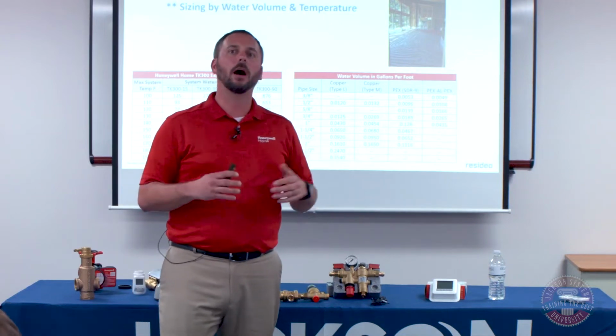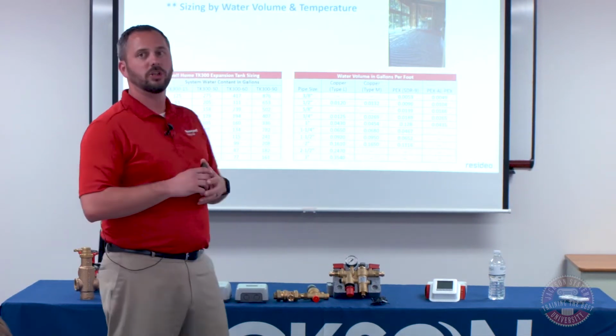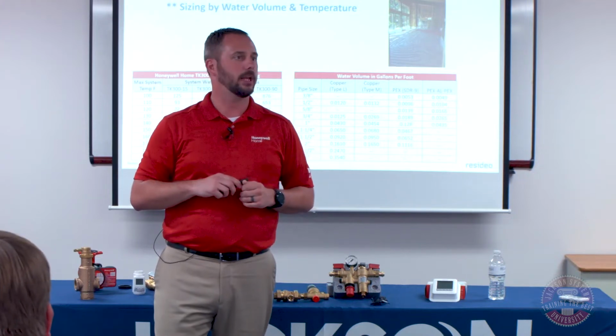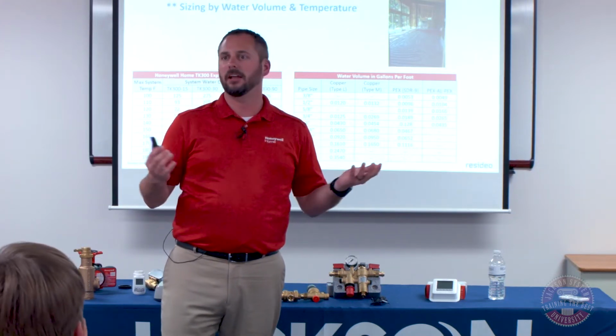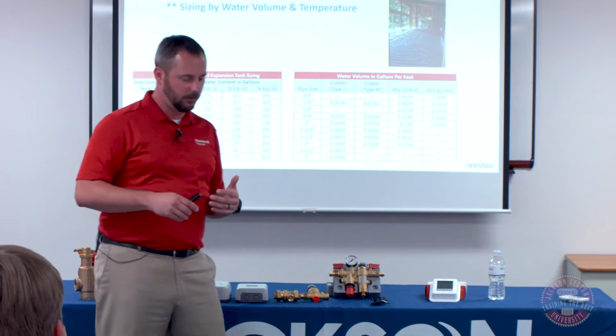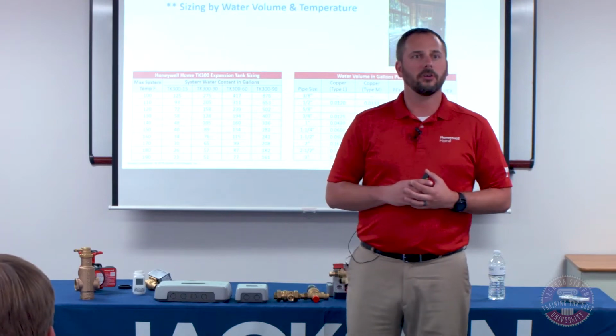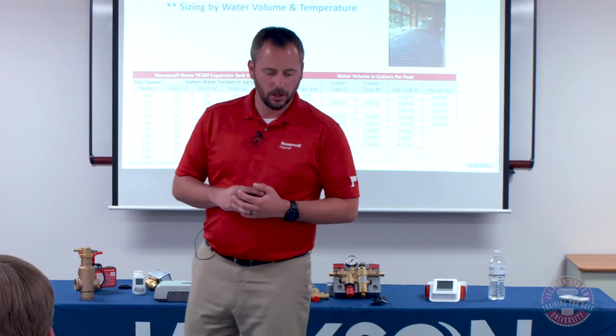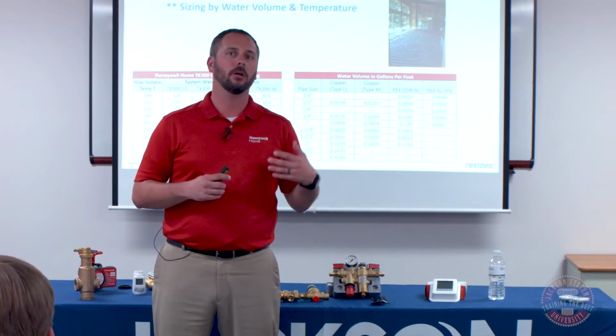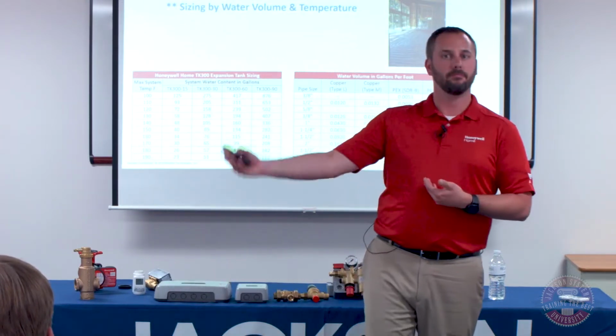The Model 30, which is a 4.4 gallon, is our most common expansion tank by far. With the Model 30, what you want to do is on the left-hand side of that column, trace down and find the maximum temperature that your system will be operating at. If we're doing an in-floor heating system, let's just say that's roughly 120 degrees. At 120 degrees, the Model 30 expansion tank can handle the capacity of roughly 158 gallons of water. So you can just start adding up where your water is. On the right-hand side, I've put the water volume per lineal foot of different types of piping. I've got copper, both type L and type M, as well as PEX and PEX-aluminum-PEX, and just get a rough idea of where you fall.